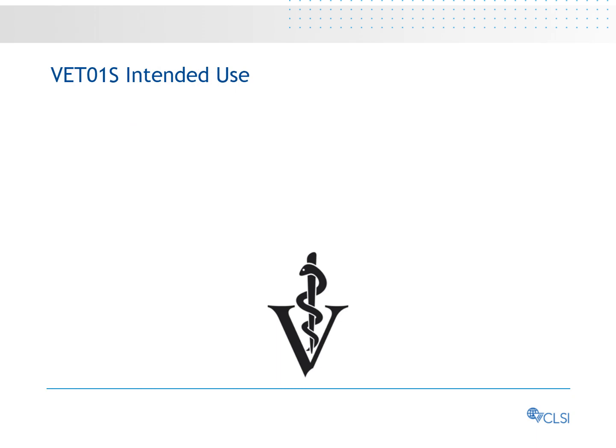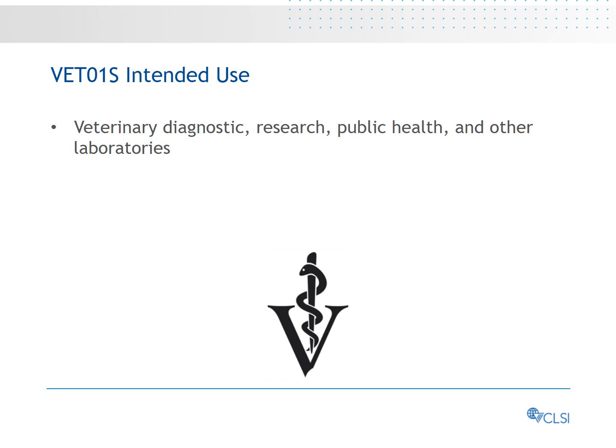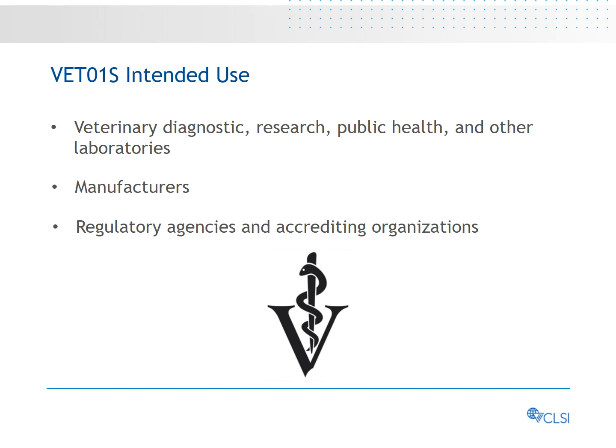VET-01S is intended to be used by veterinary diagnostic, research, public health, and other laboratories, manufacturers, and regulatory agencies and accrediting organizations. Although regulatory agencies do not set veterinary-specific breakpoints, and veterinary antimicrobial susceptibility testing equipment manufacturers do not have pre-approval or regulatory clearance requirements for veterinary isolates, those manufacturers are expected to validate their methods against CLSI reference methods. CLSI does not evaluate these data, but VET-01S aids manufacturers in developing testing devices that are clinically appropriate, safe, and effective, and provides guidance to pharmaceutical manufacturers for testing their products for veterinary application.